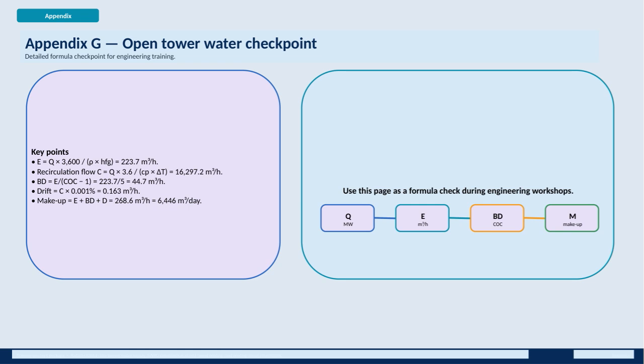Finally, the total makeup water needed is the sum of evaporation, blowdown, and drift, which comes to 268.6 cubic meters per hour, or roughly 6,446 cubic meters daily. This is vital for ensuring continuous operation without dehydration of the system. This page serves as a handy formula reference during our engineering workshops, enabling precise calculations essential for maintaining efficient and sustainable cooling tower operations.